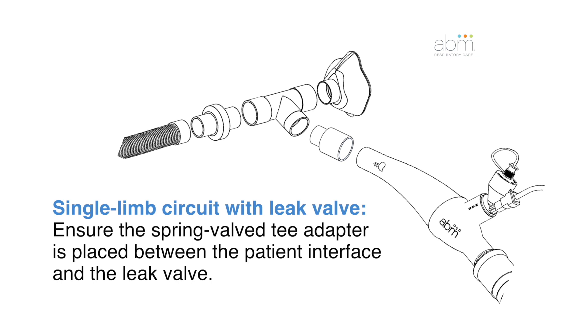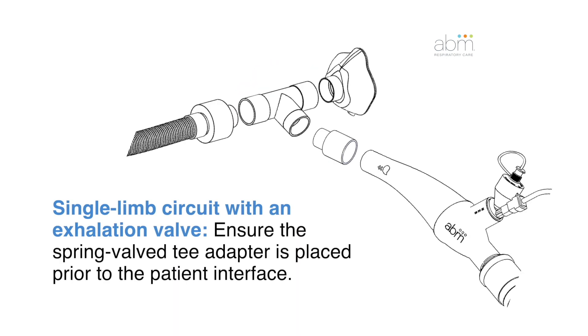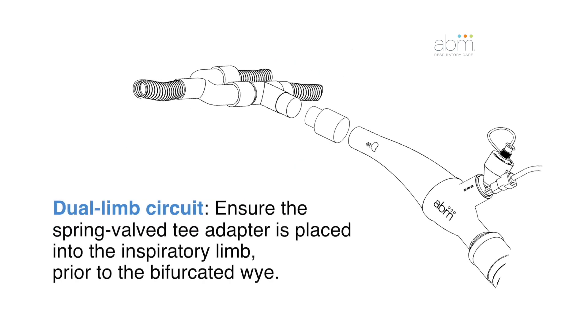If using a single-limb circuit with a leak valve, ensure the spring valve T-adapter is placed between the patient interface and the leak valve. If using a single-limb circuit with an exhalation valve, ensure the spring-valved T-adapter is placed prior to the patient interface. If using a dual-limb circuit, ensure the spring-valved T-adapter is placed into the inspiratory limb prior to the bifurcated Y.